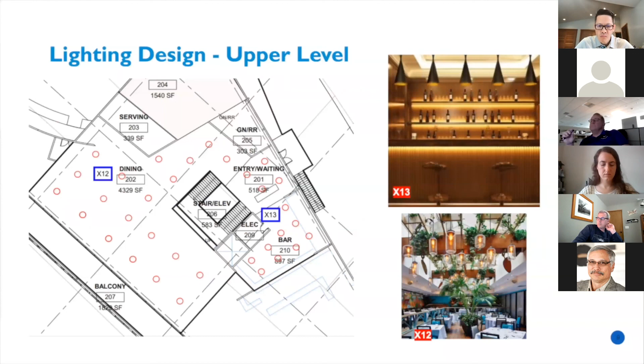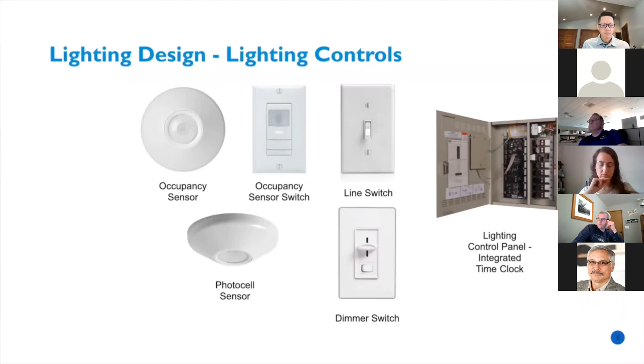atmosphere for the space. When designing the lighting, we also needed to include lighting controls. We included a lighting control panel with an integrated time clock, line switches, and dimmer switches. We included two types of occupancy sensors, which turn on when people are occupying the space. The occupancy sensor switch is used in smaller spaces and is wall-mounted, while the occupancy sensor is used in larger spaces and is ceiling-mounted.